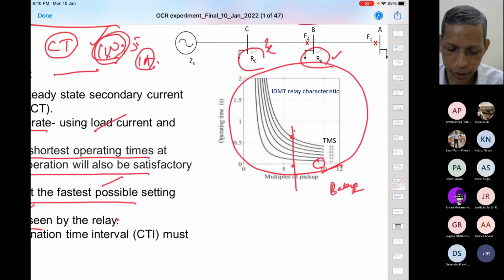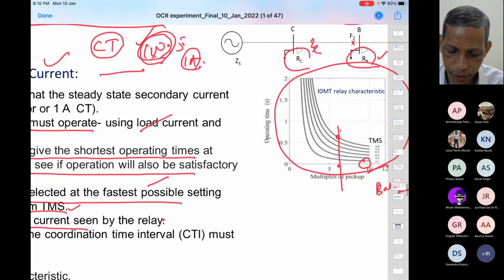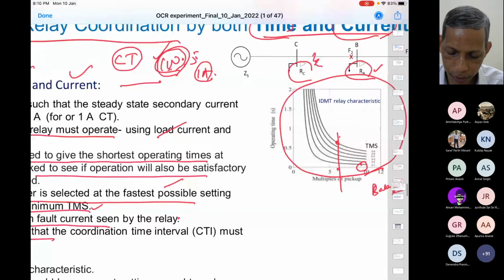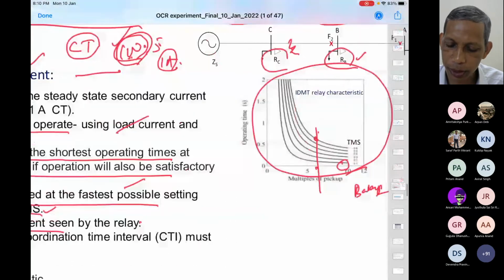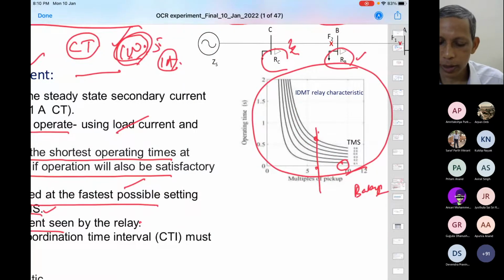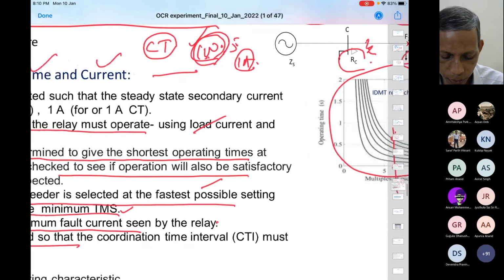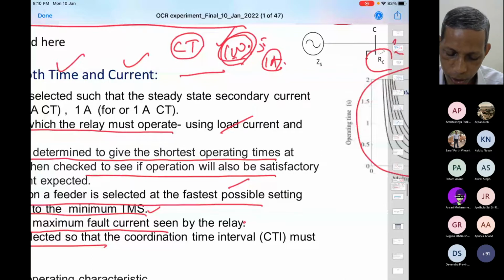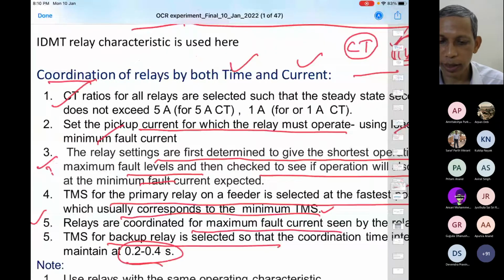Now, what happens in this case? This is the problem. So we have to take the lowest curve for the extreme end relay, and then the other relays go on adding upon that. The other important point, the fifth point, is that relay coordination should be done for the maximum fault current seen by the relay.